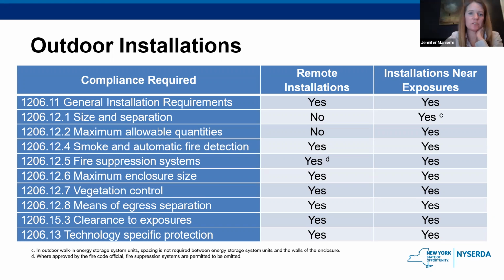Yep, so if you have that 100-foot clearance, you get a little bit more leeway. You don't have to comply with the size and separation or the maximum allowable quantities. A couple little exceptions in here too. So for installations near exposures, you'll see the little subnote here. In outdoor walk-in energy storage system units, spacing is not required between the units and the walls of the enclosure. So there's like little things like that throughout it.